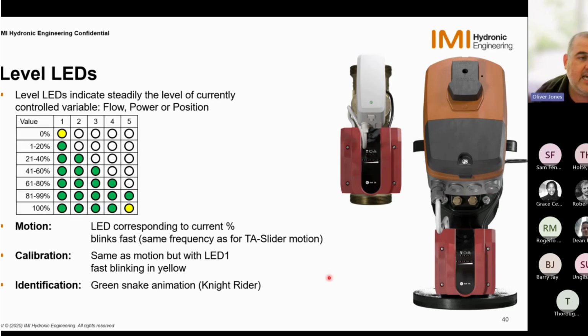presently. And then identification. So within the app itself, we can force what we call the green snake animation or Knight Rider. So this is actually a run of blinking lights which runs from front to back, and you can physically see that on top of the valve. So if you've got multiple valves and you want to make sure you're working or setting up the correct one, you can run the indication process.